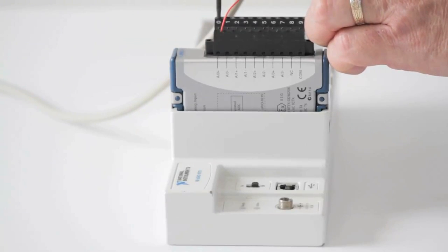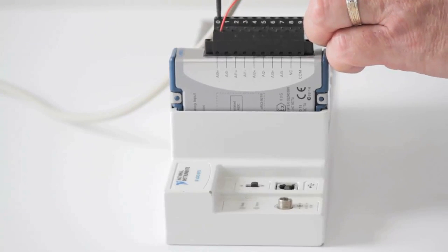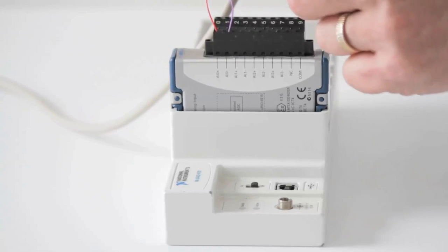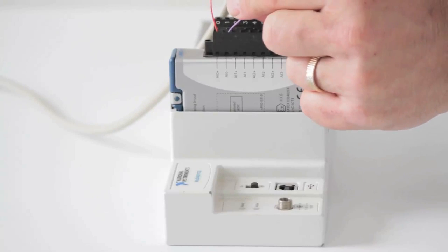In this case, sensor isolator output channel 1 will connect to the DAQ analog input 0. Now I'll do this for the remaining channels.